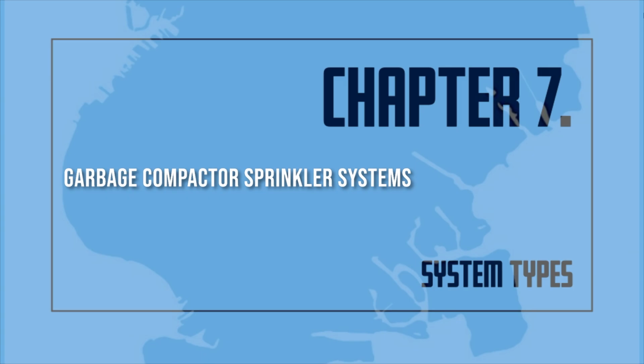All indicating valves in the compactor sprinkler system shall be sealed open. A minimum of 6 extra sprinkler heads with the appropriate wrenches shall be available to replace any opened or damaged sprinkler heads. Opened or damaged sprinkler heads shall be replaced immediately. A garden hose connected to a water supply shall be kept in the compactor room. This hose may be used to put out small fires or smoldering material in the compactor room.